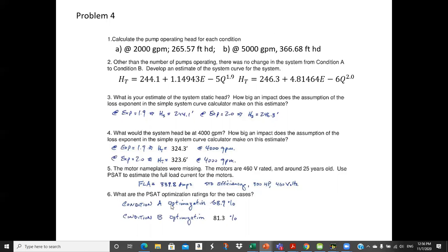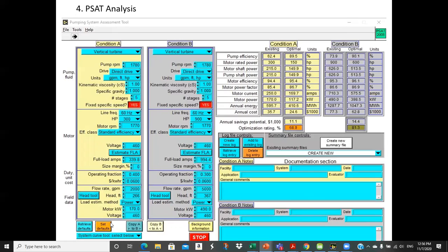And then the optimization rating for condition A, which is at the 2,000 GPM, that pumping operation is 68.9% of the optimal. And at condition B, we're 81.3. Okay. And so this is the PSAT analysis. All the data put in. This is where you just estimate full load amps. There's the 339.8 in this condition. There's the optimization ratings. There's operating cost. We spend 40% of the time at 2,000 and 30% of the time at 5,000, so you can see the relative amount. So this is well over $100,000 between these two conditions. That's just for 70% of the year.